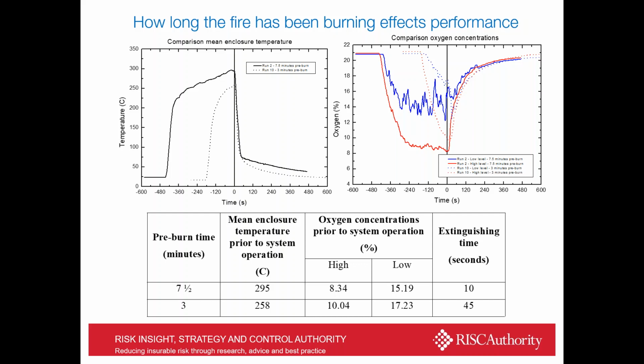So the consequence of burning for longer is that we see in the left-hand graph that the mean temperature of the enclosure is higher. It's 295 degrees as opposed to 258 degrees. The other consequence of allowing a fire to burn longer is that it's consumed more oxygen from the enclosure before the system operates than a shorter pre-burn time. And at its lowest, you can see high up in the compartment, it reaches a level of just over 8% oxygen, whereas with a 3-minute pre-burn time, it's 10%. And when we activate the system, we see a difference in performance in the time to extinguish that fire. So burning the fire for longer, we extinguish it in 10 seconds, whereas burning it for a shorter period of time, it takes 45 seconds to go out. So I think that's all very logical, but again, counterintuitive. We're rather used to detecting and tackling fires earlier because they're easier. But here's a case where leaving them longer makes them easier for this type of system.